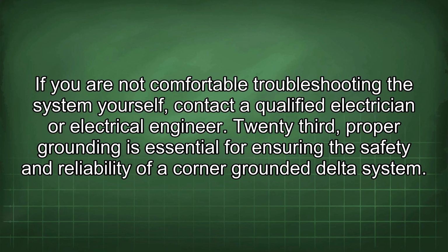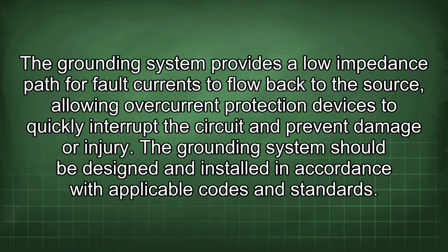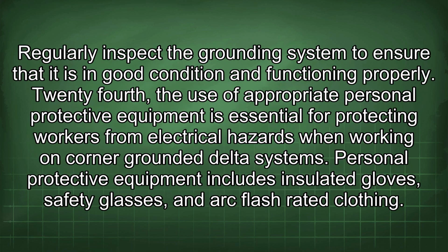23rd, proper grounding is essential for ensuring the safety and reliability of a corner-grounded delta system. The grounding system provides a low impedance path for fault currents to flow back to the source, allowing overcurrent protection devices to quickly interrupt the circuit and prevent damage or injury. The grounding system should be designed and installed in accordance with applicable codes and standards. Regularly inspect the grounding system to ensure that it is in good condition and functioning properly.